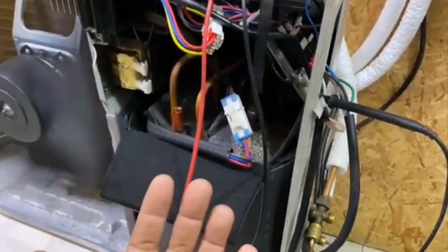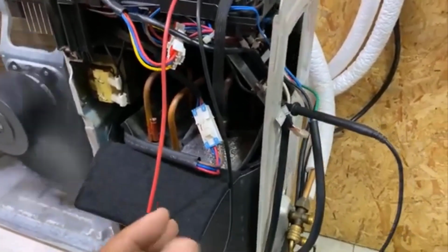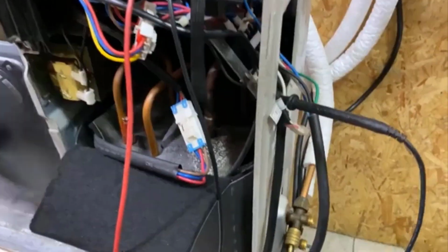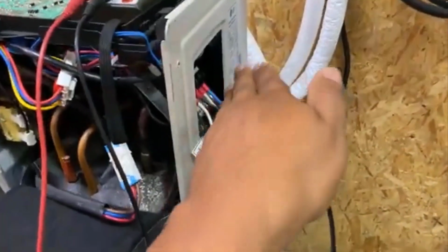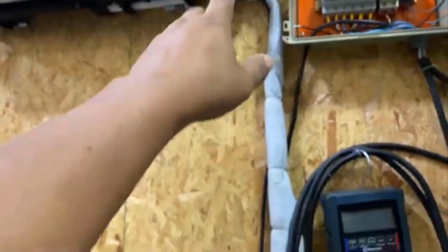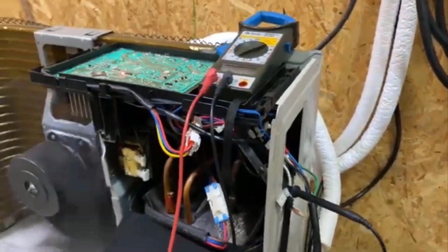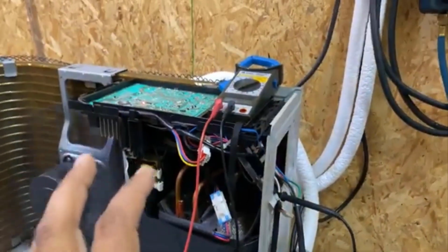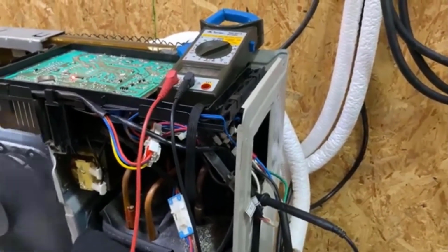Inspect electronic boards. Examine the evaporator and condenser boards. Look for signs of burning, swollen capacitors, or loose components. Test the boards: temporarily replace the suspect board with a new or tested one to rule out failures. Test voltage and grounding: measure the voltage between the communication terminals and confirm that it is within the standard indicated in the manual. Make sure that the system is properly grounded.